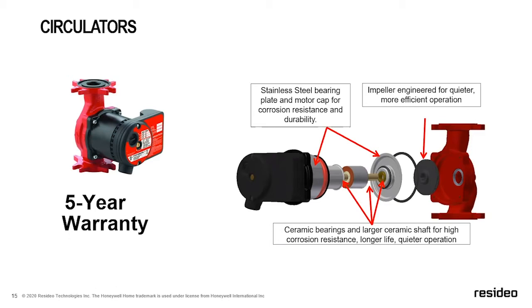This is a wet rotor pump, so keep that in mind when installing it. The bearings are ceramic and they're larger. Ceramic shaft for higher corrosion resistance, longer life, quieter operation. But one of the main things I want to point out is on the left here. You can see the red flange on the bottom and top of that pump. That's a 4-way flange. So you've got more opportunity to install this, more options, makes it more universal.